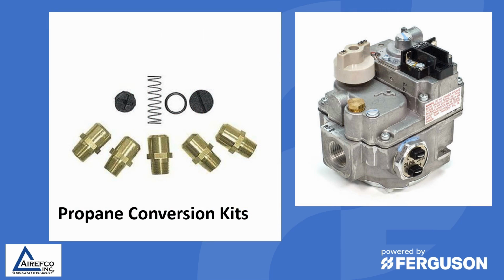We mentioned earlier accessories that need to be installed on certain gas applications. I got a call the other day from a tech who was working on a furnace that was tripping on the limit switch and it was running hot. And we determined that it was on propane gas, but had never been converted to propane. So there are propane conversion kits that usually consist of the change of orifices for each burner, and then usually a spring that goes into the gas pressure adjustment port on the gas valve. So make sure that all the accessories that you need for your installation have been done properly and that the gas furnace is set up correctly for proper operation.